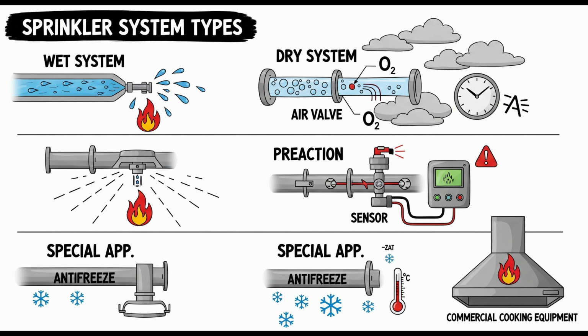How is it monitored continuously? Each dry pipe valve must have a low-high supervisory pressure switch. This device triggers a supervisory signal, not a full fire alarm, but a trouble signal if the air pressure goes outside the acceptable range. What are the trigger points for low and high?